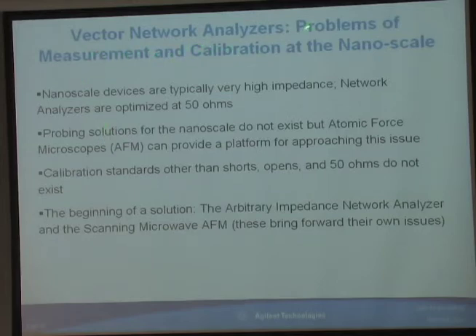This is about vector network analyzers, and the problem of measurement and calibration at the nanoscale. I already mentioned a little of this. Nanoscale devices are typically very high impedance. Network analyzers are optimized at 50 ohms, so you get low sensitivity of measurement. Probing solutions for the nanoscale don't exist—but yes, they do, because there's a thing called an atomic force microscope, which is basically a probe. So if we can connect to that probe, we now have a nanoscale probe.